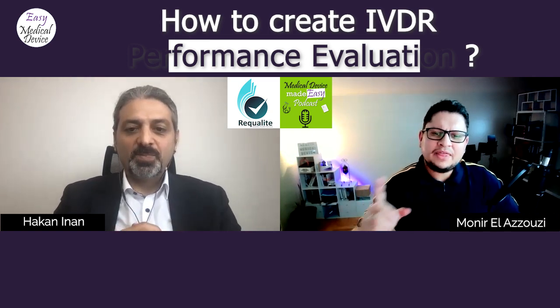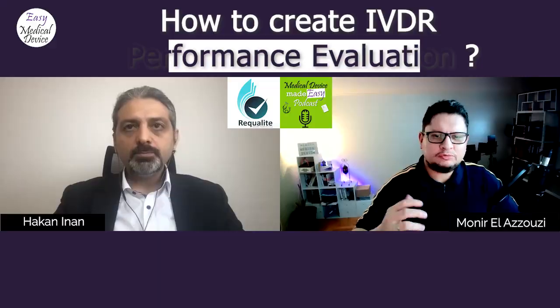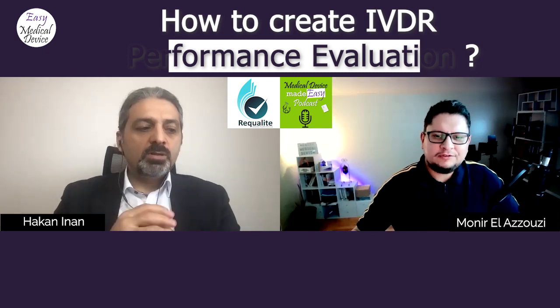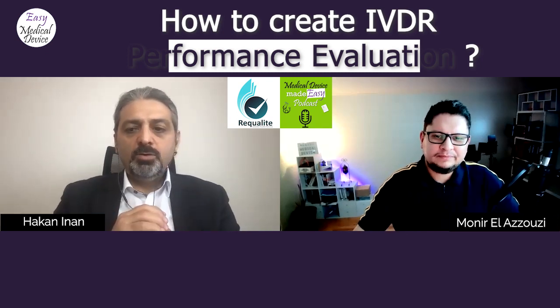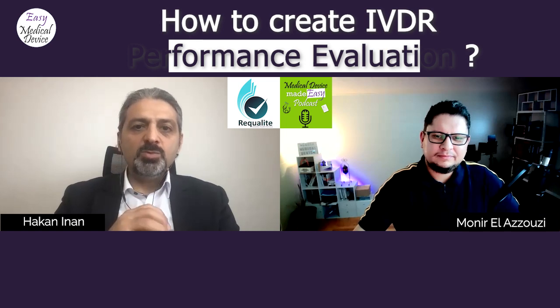And did you have that on the IVDD? Did you have the guidance? Because for example, for the CER, we had the MedDev 2.7/1 revision 4. So do you have a similar document for IVDD? No, not really. The documents that we rely on for performance evaluation, as of now, there are 4 main documents, if I may say. One is MedDev 2.7/1 revision 4, which is basically for medical devices.